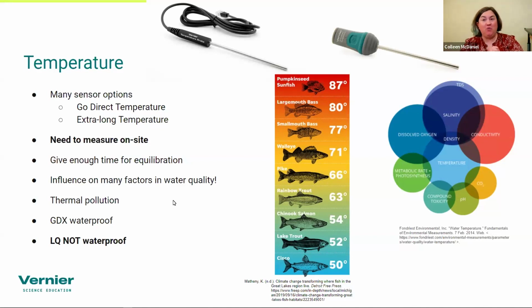Another thing to note with these water quality sensors is their waterproofness. The Go Direct version of the sensor is waterproof, while the LabQuest version is not waterproof, more water resistant than waterproof. If you submerge the sensor beyond the metal shaft into the plastic housing on the LabQuest sensor, you're going beyond the area it can function in, because that's where all the electronics are, and those aren't covered.